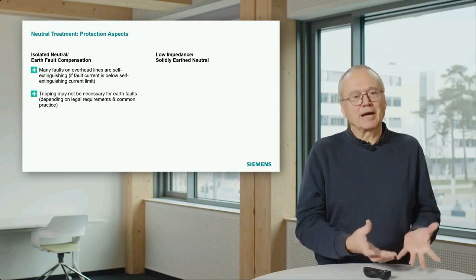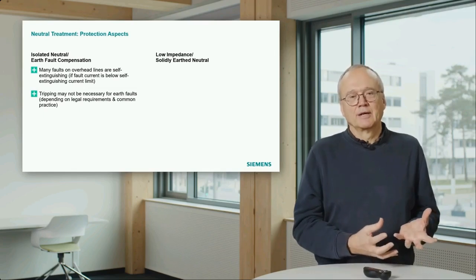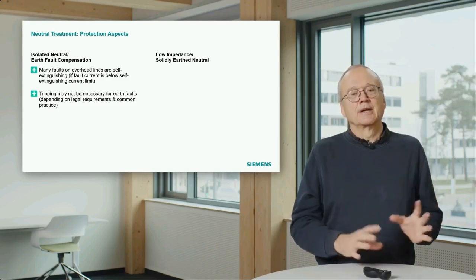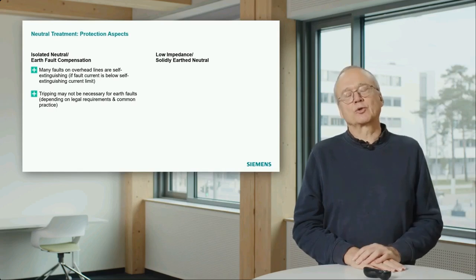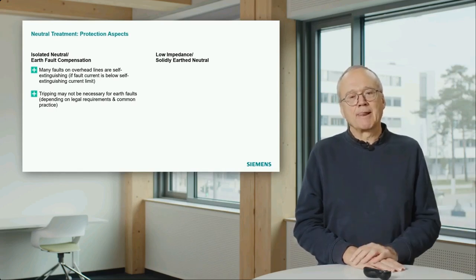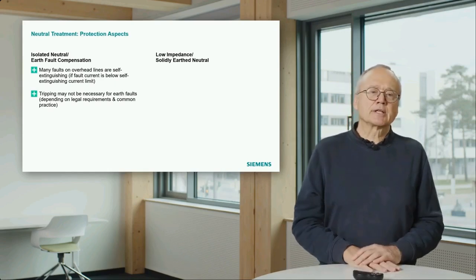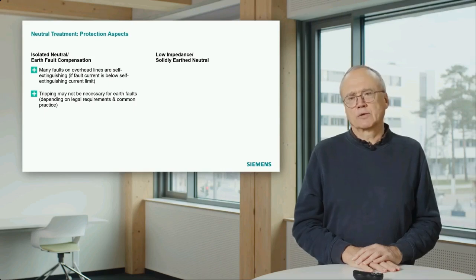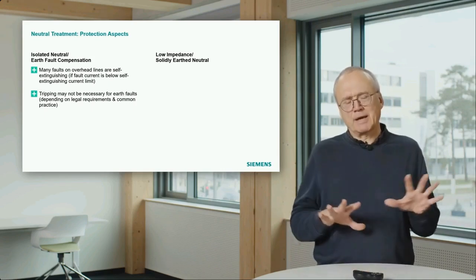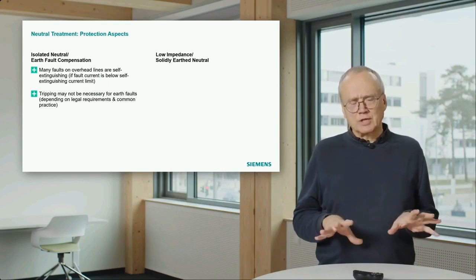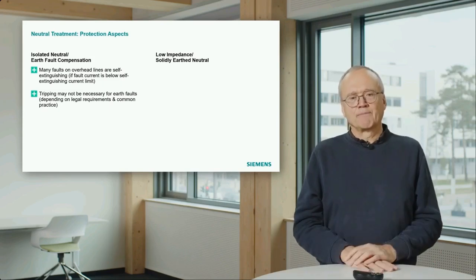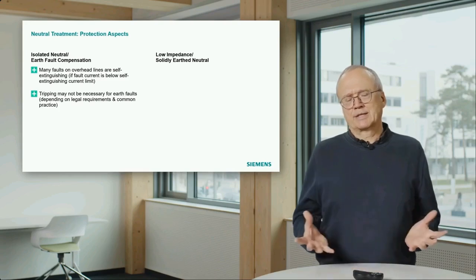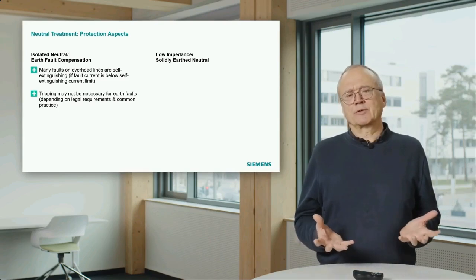That means after some time something will happen down there. So continuous operation for infinite time is not possible. It's not necessary to trip the fault in a milliseconds time, but operation for longer time also has some limitations. And as I mentioned, it depends on the legal requirements. That means if you compare the concepts you see in different countries, some countries allow that, other countries require tripping. And to the end, that is a risk evaluation.